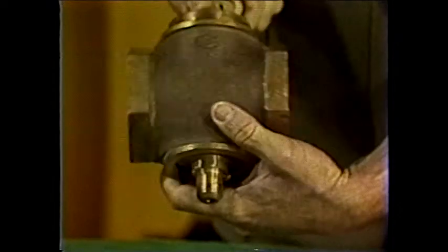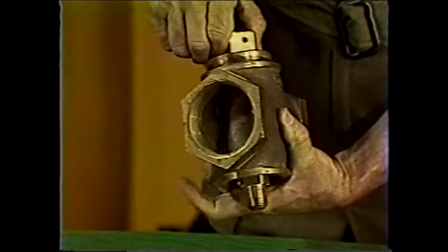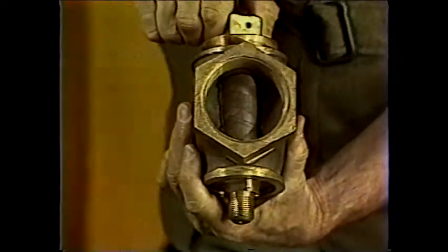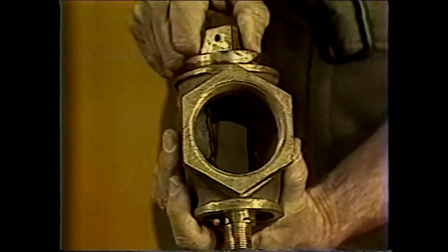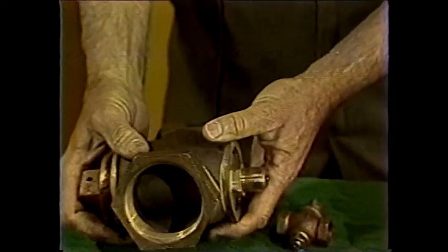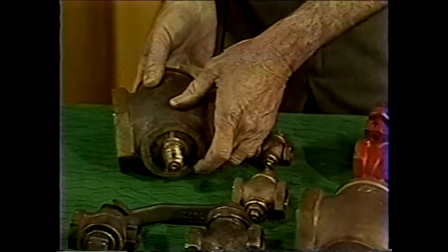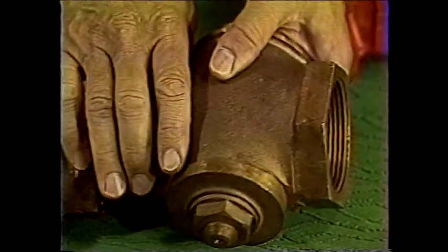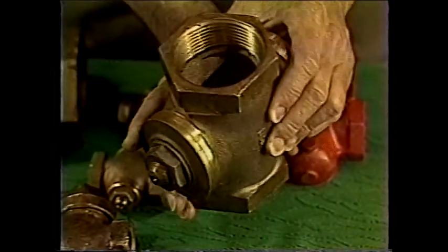By turning the handle a quarter turn, it goes from full open to completely closed. Plug valves are relatively economical, but are used primarily in situations requiring full-on or full-off operations. They are not normally used in applications which require frequent operation, since the metal-to-metal contact tends to cause faster wear than in certain other styles of valves. However, lubricated plugs tend to overcome this problem. There's very little pressure drop in the plug valve.